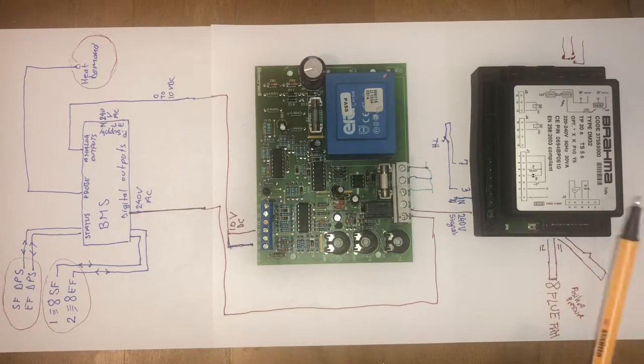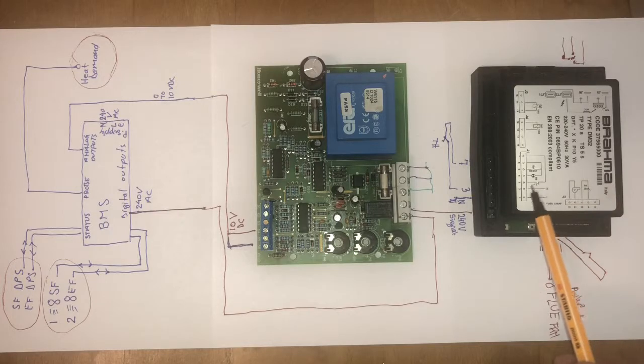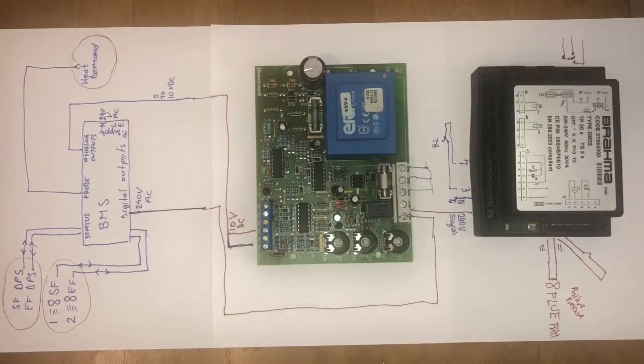You're supposed to have 240 volts, and in between 3 and 7 you have to have a closed circuit, because if you don't have a closed circuit in between 3 and 7, it means the thermostat is open or you do not have the heat demand. You don't necessarily have to have a thermostat. If you use a jump, you will run forever until it will pop out, maybe high limit, safety, blah blah blah.